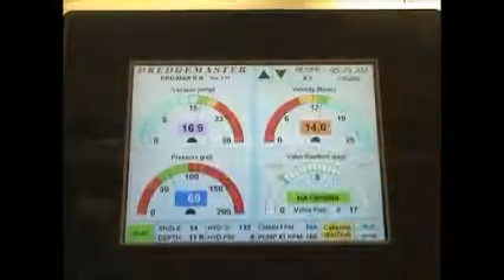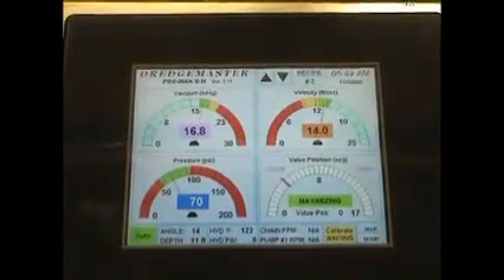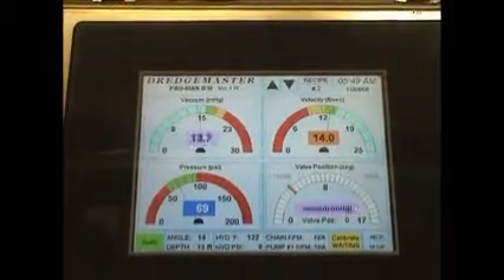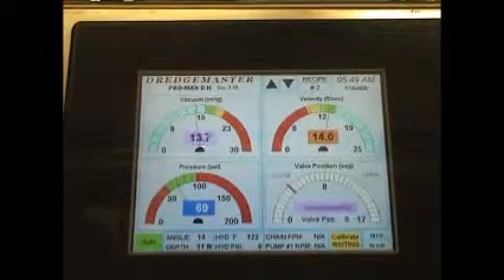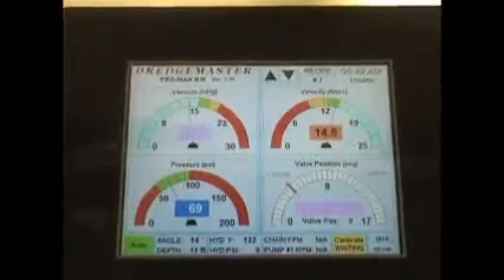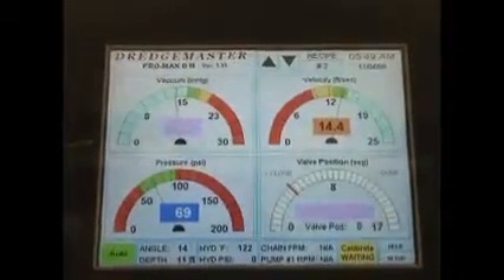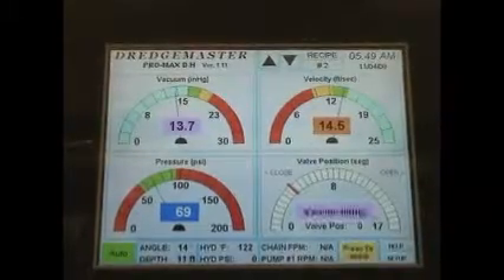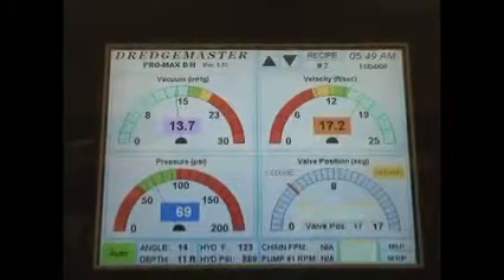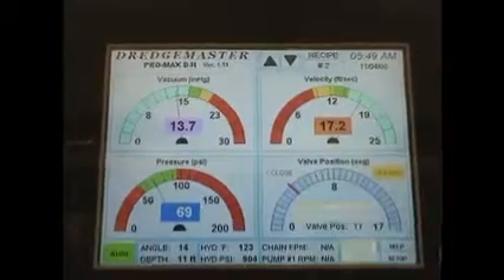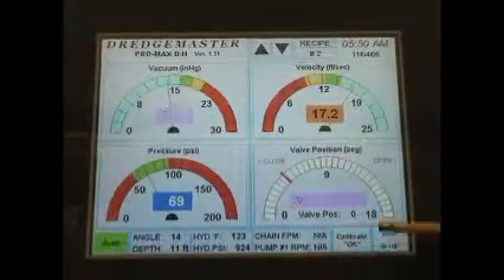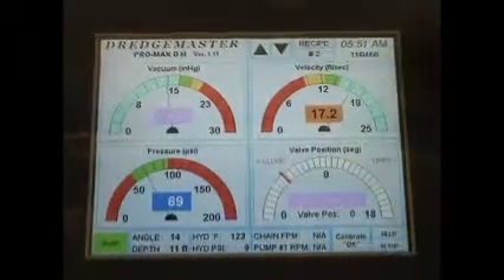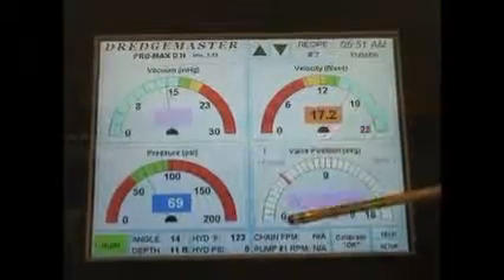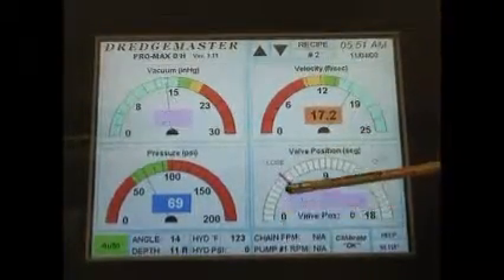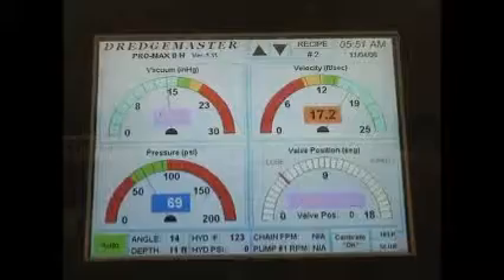So we're going to go back to our main screen. The dredge operator is going to lighten up his load again. Notice we have the calibration waiting light that automatically comes on because we changed that 2-speed set point, so it's going to want to go through its calibration process. After the calibration process is completed, we'll demonstrate how the valve is going to open up more rapidly between 0 and our 2-speed set point.